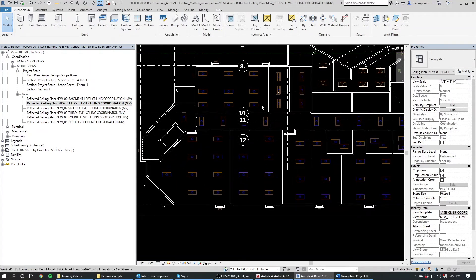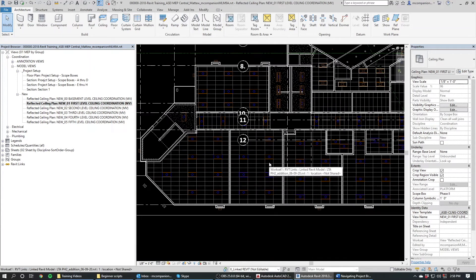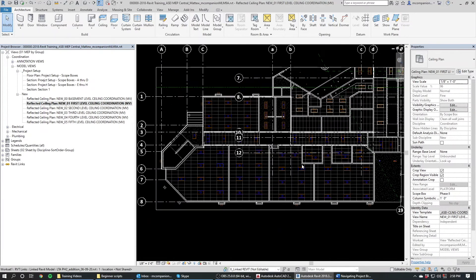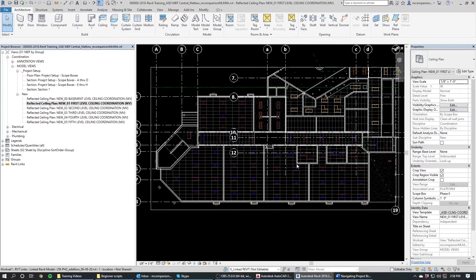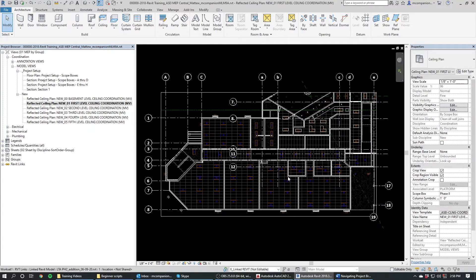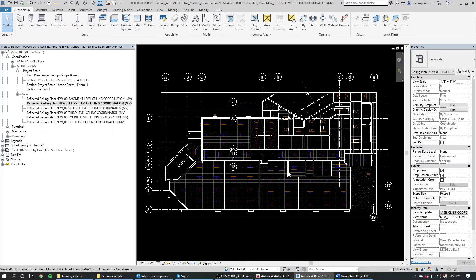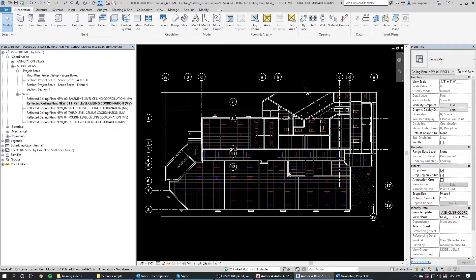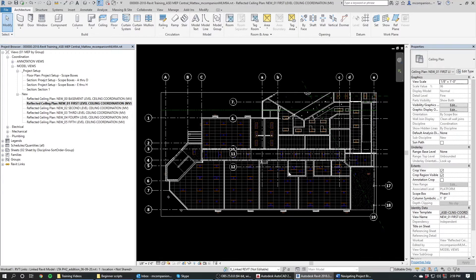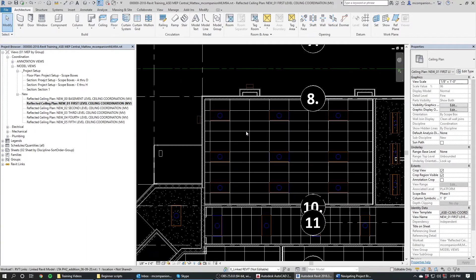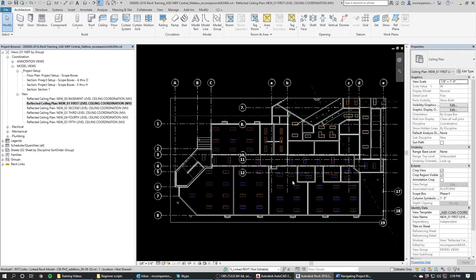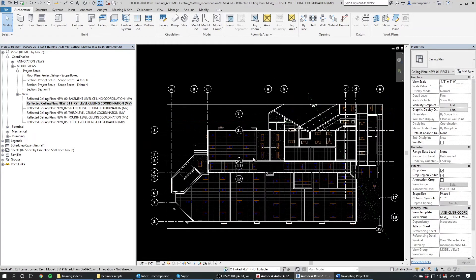The only thing you should be seeing on this view are diffusers and lights. So you should have no problem when the architect sends us a new model update and you come in here and you want to go verify that they didn't change their ceilings around, which happens to us all on all of our jobs pretty much. Even in CAD, the difference is in CAD you have your entire sheet with all of the work basically. So you've got all your notes, all your ductwork, all your equipment, all everything is on there. So it can sometimes get a little convoluted to be able to see your diffusers and you can miss them. If you come into this view, all you see are lights and diffusers in the ceiling. So you come in here, you zoom into the room. Are your diffusers still in the grid? Yes. Awesome. Moving on. It's like super easy to do your update coordination for your mechanical diffusers.